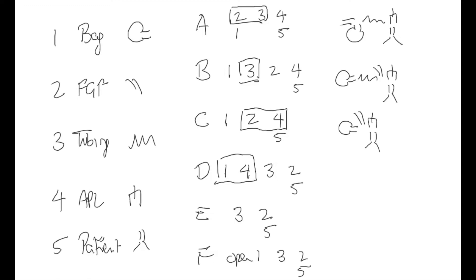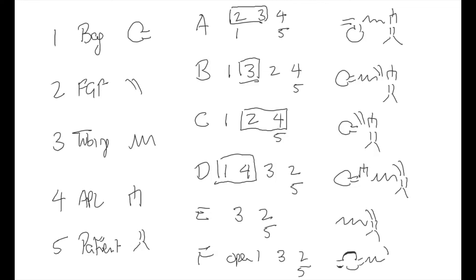D is the bag, the APL valve, the tubing, the fresh gas flow, followed by the patient. E is tubing, fresh gas flow, followed by the patient. And F is an open bag, followed by the tubing, fresh gas flow, and then the patient. And that is how you draw the Mapleson circuits in under 2 minutes.